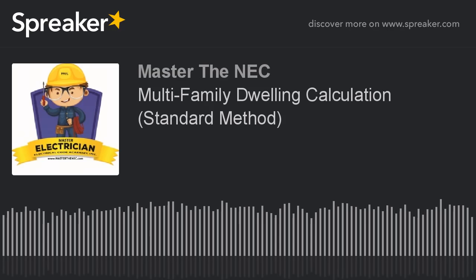So 25% of 15,000 is 3,750. Now we're going to add all three of those values up. So it's 3,000 plus 40,950 plus 3,750 for a total of 47,700 VA. All right, now that is our general lighting load. We write that down. That's the first part of our equation.